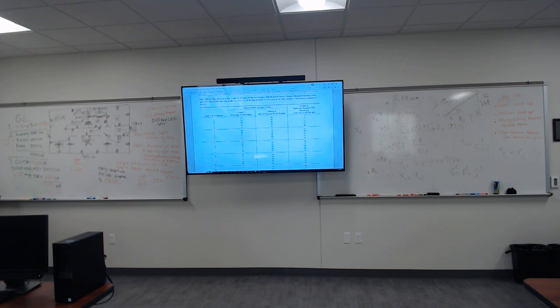Now, number 7. All right, I got that information as well. The AC or the heater. Let's see what this says. Article 220.60. All right, non-coincident load. Where it is unlikely that two or more non-coincident loads will be used simultaneously, it shall be permissible to use only the largest load that will be used at one time for calculating the total load of a feeder or service.